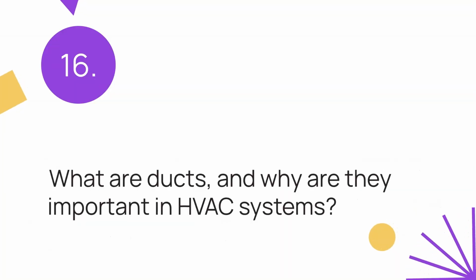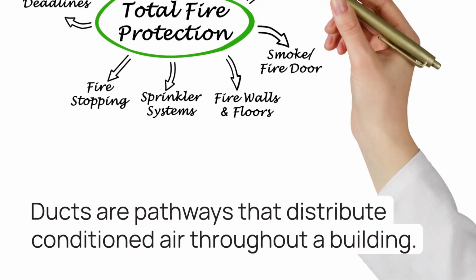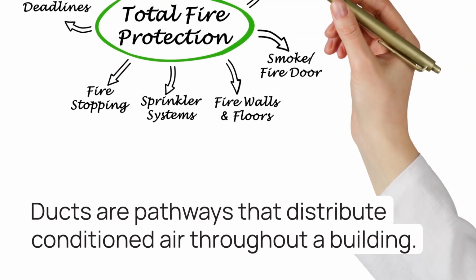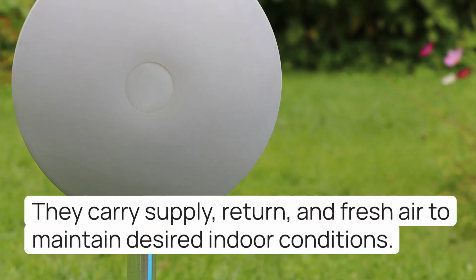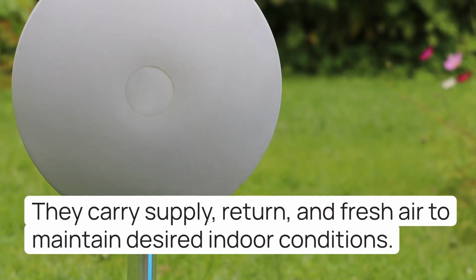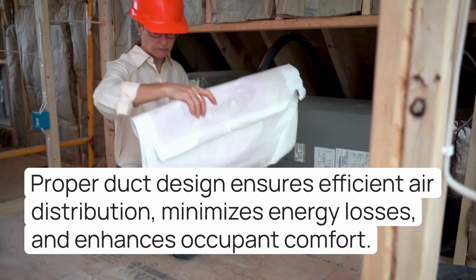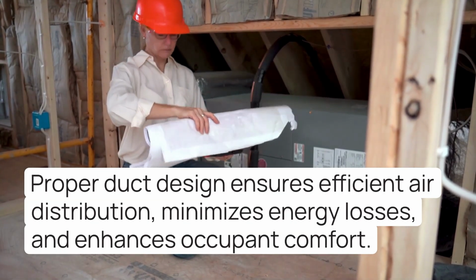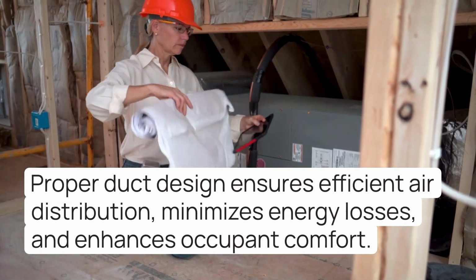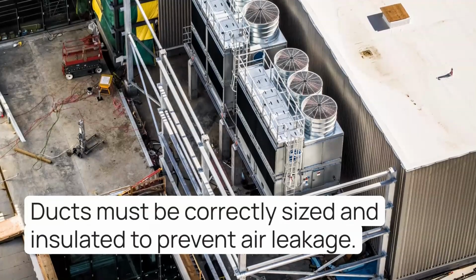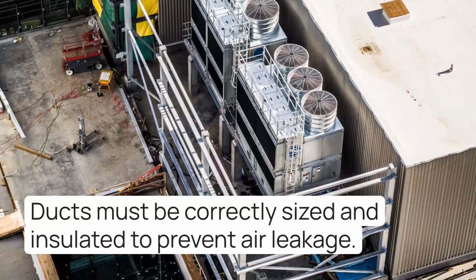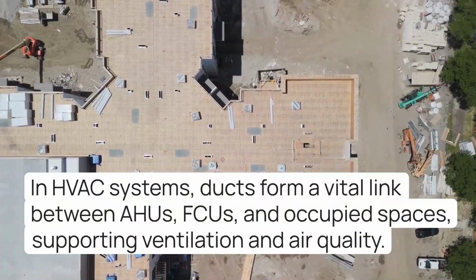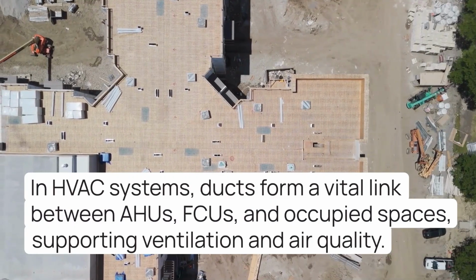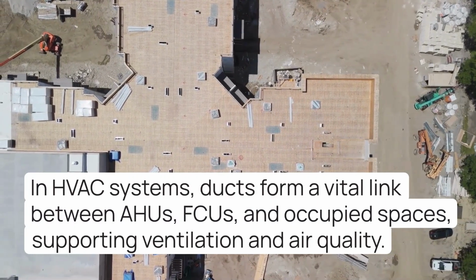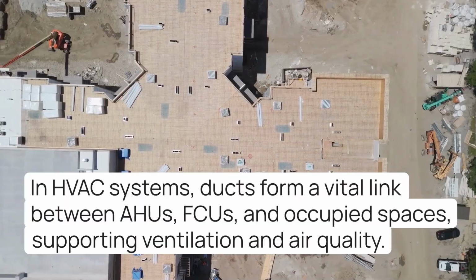16. What are ducts and why are they important in HVAC systems? Ducts are pathways that distribute conditioned air throughout a building. They carry supply, return, and fresh air to maintain desired indoor conditions. Proper duct design ensures efficient air distribution, minimizes energy losses, and enhances occupant comfort. Ducts must be correctly sized and insulated to prevent air leakage. In HVAC systems, ducts form a vital link between AHUs, FCUs, and occupied spaces, supporting ventilation and air quality.